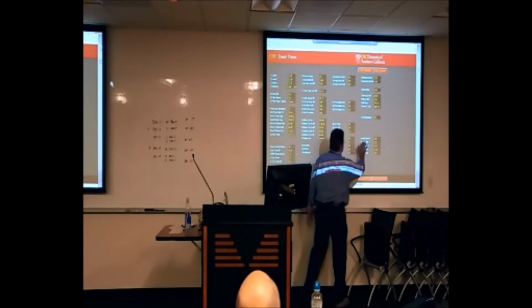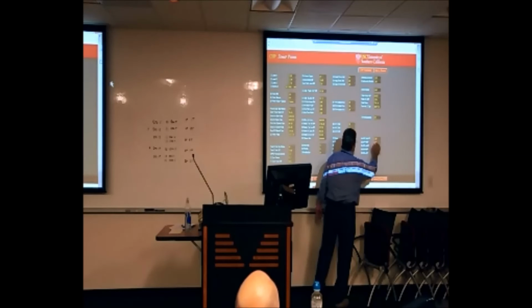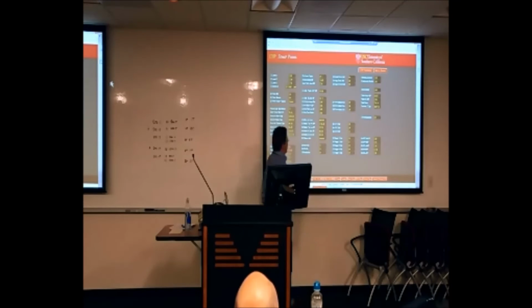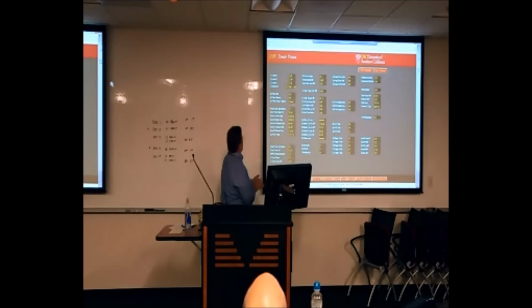The calculated DP set point is reflected right here, and so this is based right now on where that delta T is. It says we'd like to be controlling to 2.58, but right now we're in the fixed speed mode. So it's not controlling to that delta P, it's actually controlling to just a straight 75% at this moment.